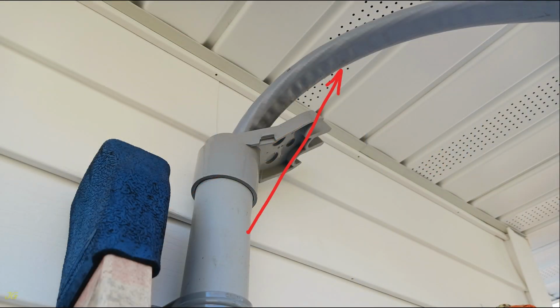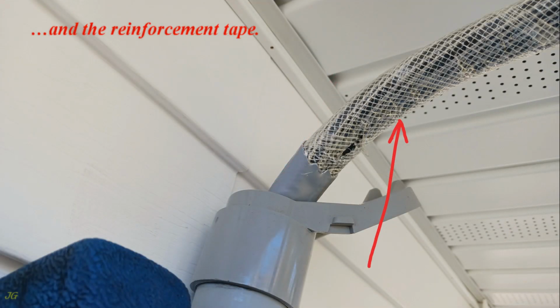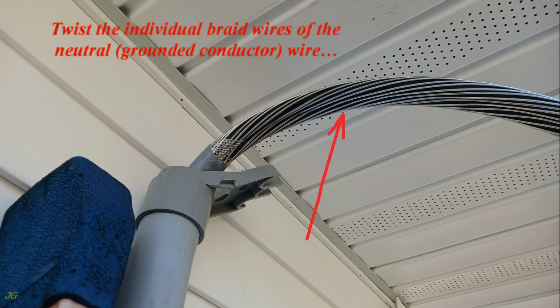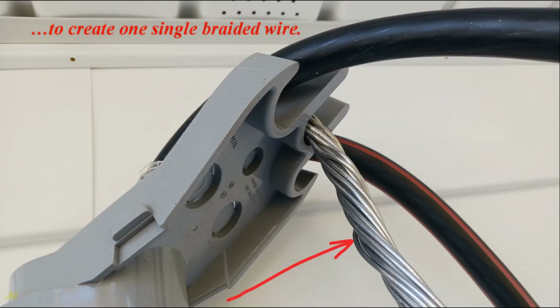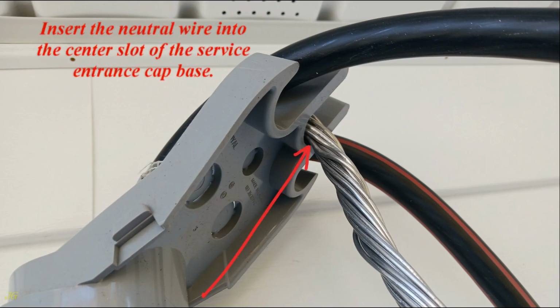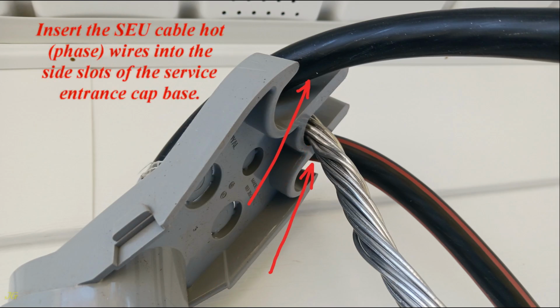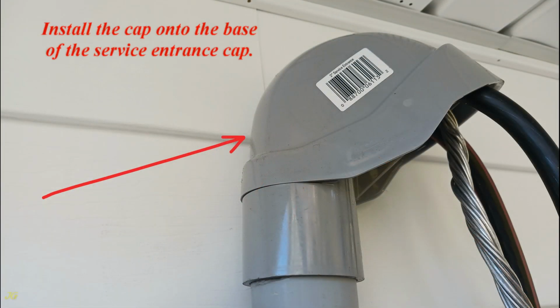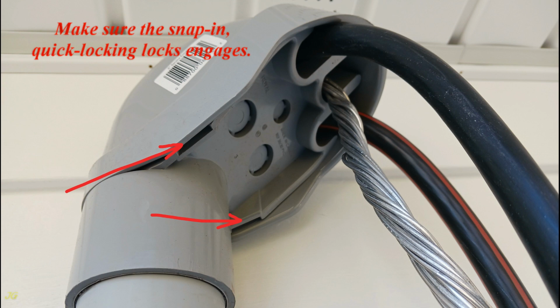Remove the cable sheath and the reinforcement tape. Twist the individual braid wires of the neutral, grounded conductor wire to create one single braided wire. Insert the neutral wire into the center slot of the service entrance cap base. Insert the SEU cable hot phase wires into the side slots of the service entrance cap base. Install the cap onto the base of the service entrance cap. Make sure the snap-in, quick locking locks engages.